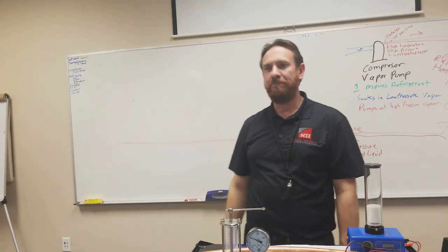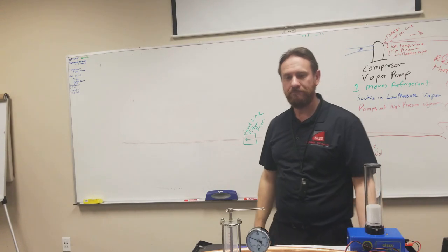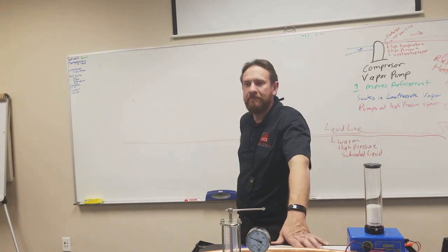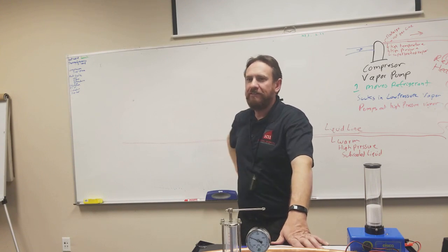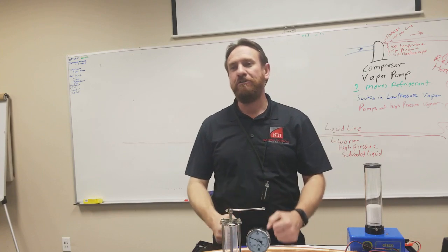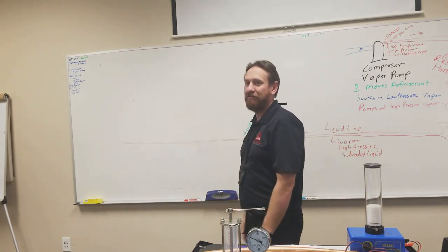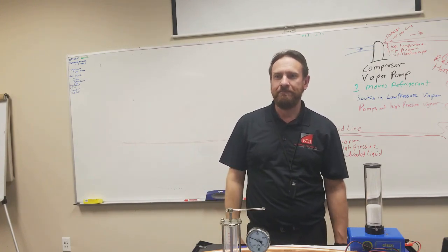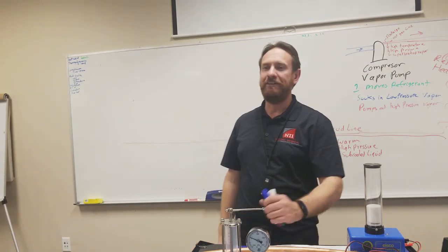So it's just protection. Just out of curiosity, let's say the difference between Florida and here, the difference in moisture in the air, do you have to install a different size, or it doesn't matter? If you do it correctly, we use a gauge when we're pulling a vacuum, when we're cleaning this out, and if we get to the correct number, it doesn't matter where you're at, you're there. It will take longer to get there if you're in Florida on a humid day though, than it would here.